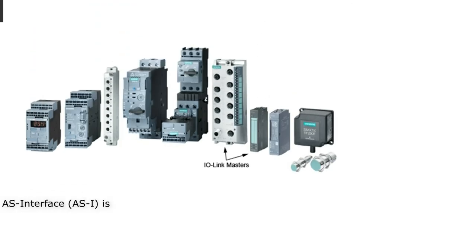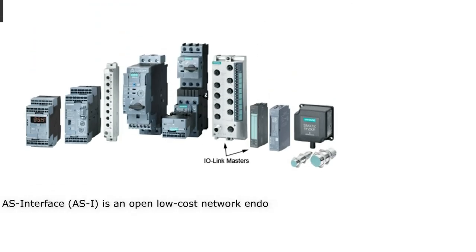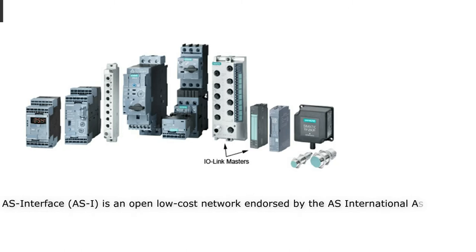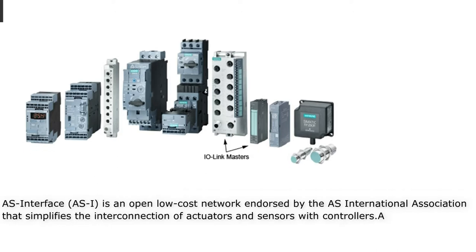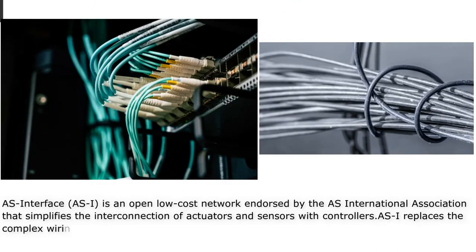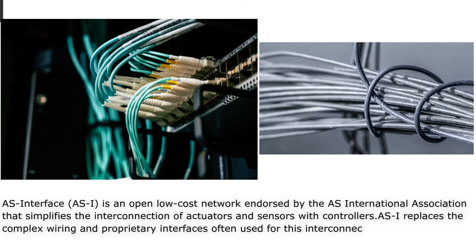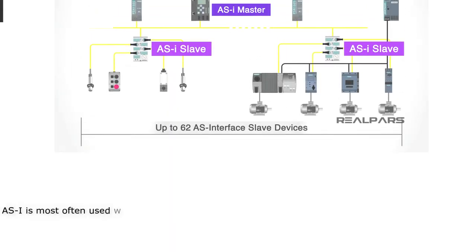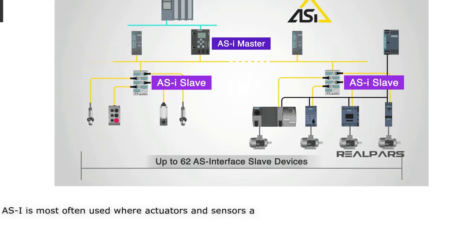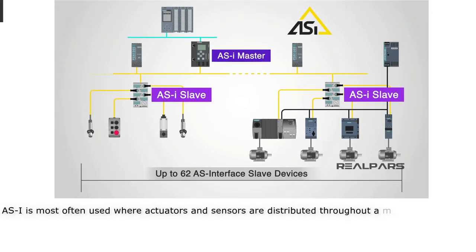Actuator Sensor Interface (AS-Interface, ASI) is an open, low-cost network endorsed by the AS International Association that simplifies the interconnection of actuators and sensors with controllers. ASI replaces the complex wiring and proprietary interfaces often used for this interconnection with only two wires, which transfer both data and power. ASI is most often used where actuators and sensors are distributed throughout a machine or facility.